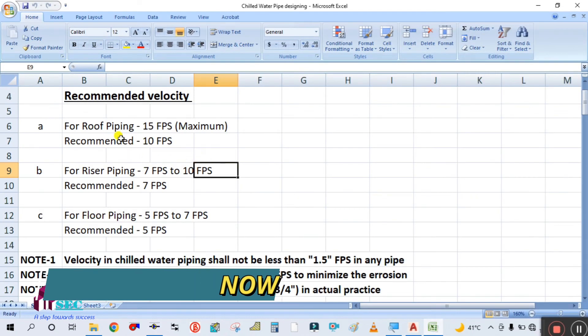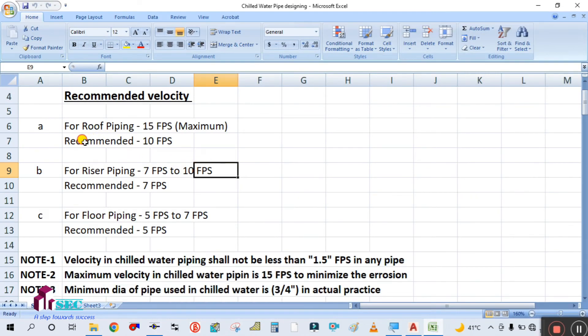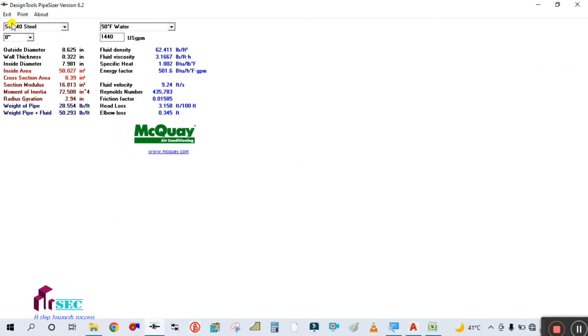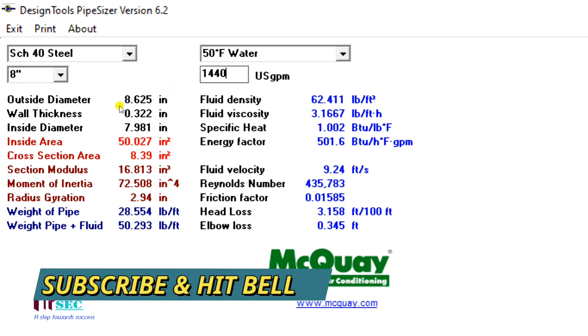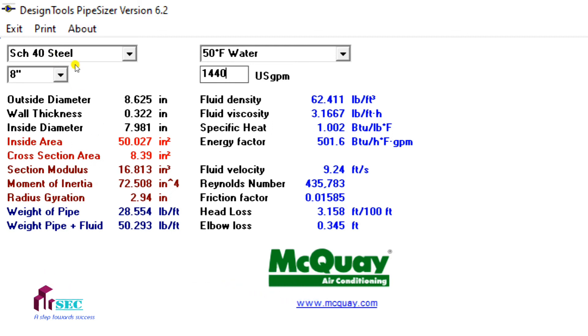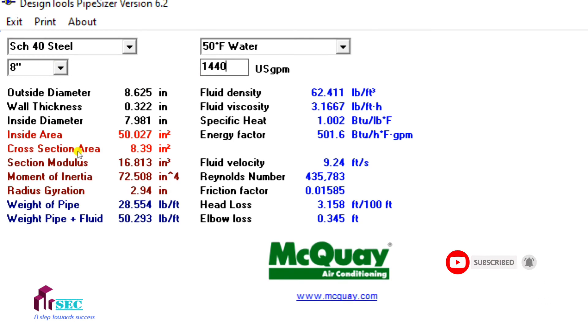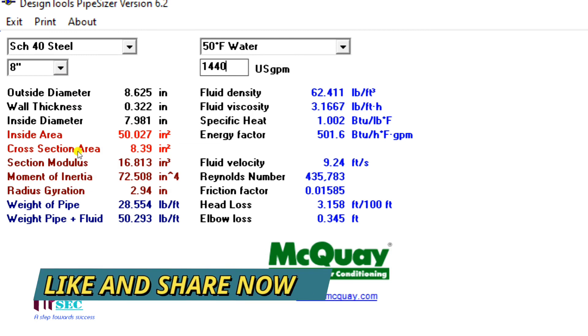This is the roof piping and the recommended velocity is 10 feet per second. You can see your pipe size is 8 inch, GPM is 1440, and fluid velocity is 9.2 feet per second. This means the condition is met — this will be your pipe size.